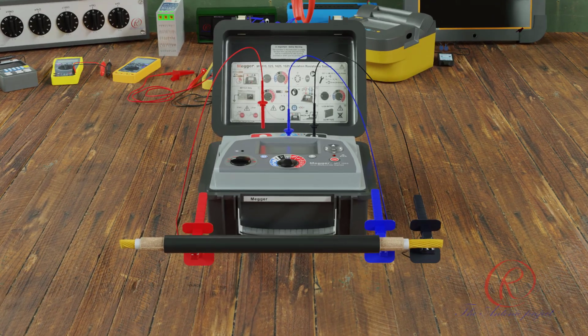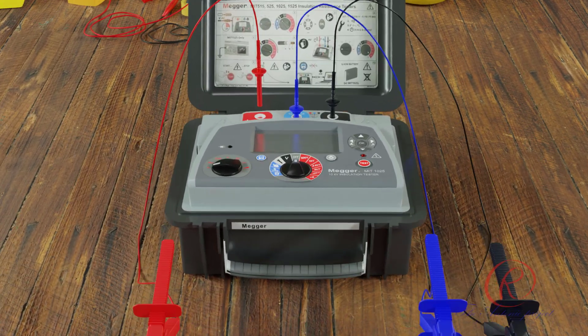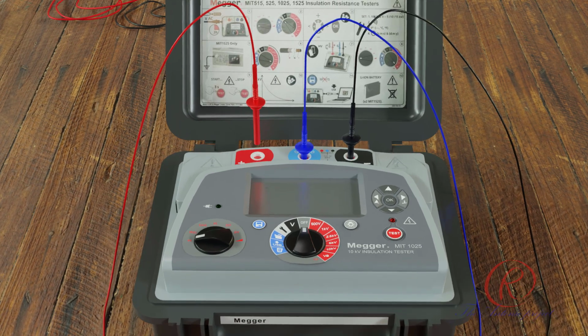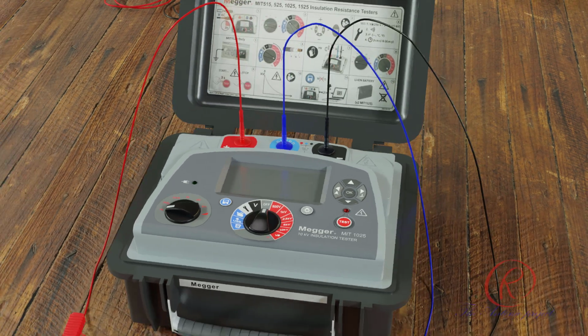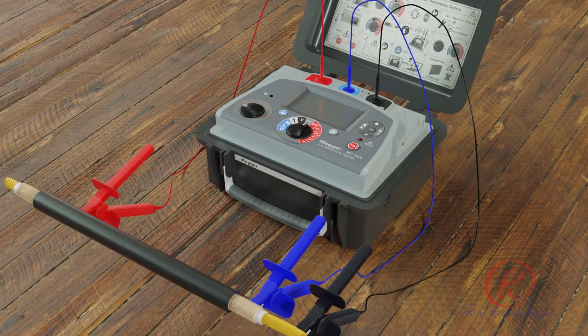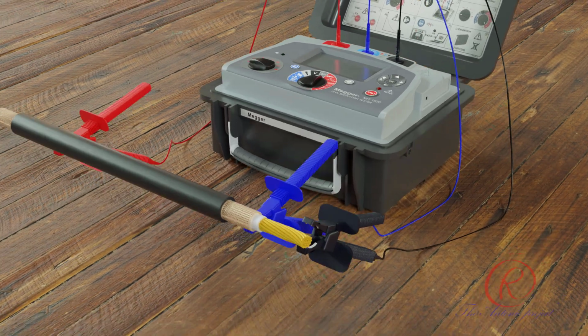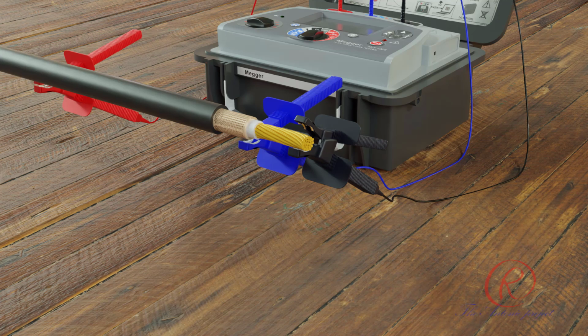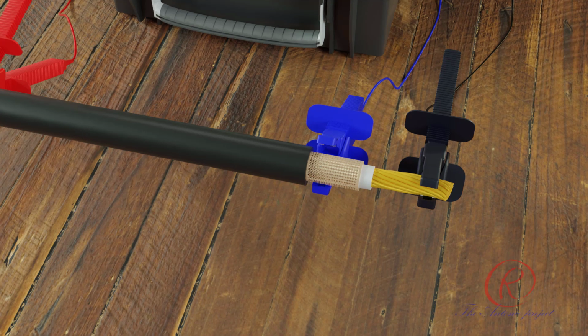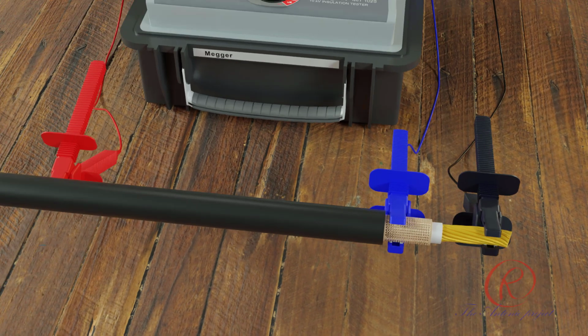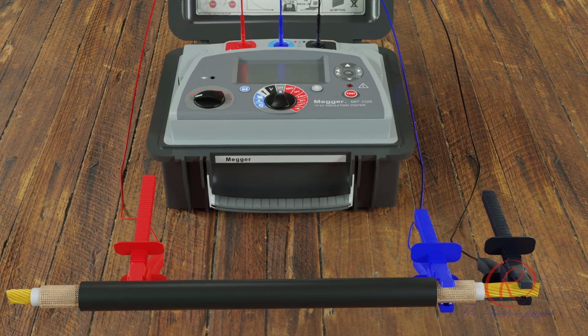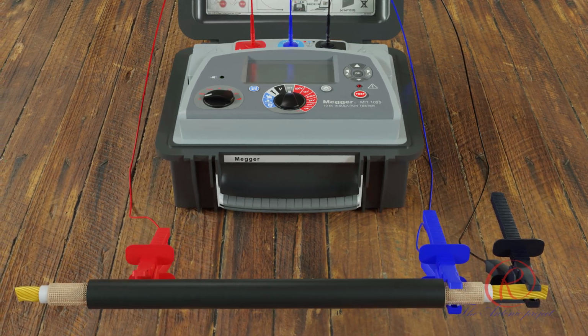For basic insulation tests and where there is little possibility of surface leakage affecting the measurement, it is unnecessary to use the guard terminal. For example, if the insulator is clean and there are unlikely to be any adverse current paths. However, in cable testing, for example, there may be surface leakage paths across the insulation between the bare cable and the external sheeting due to the presence of moisture or dirt, where it is required to remove the effect of this leakage, particularly at high testing voltages.